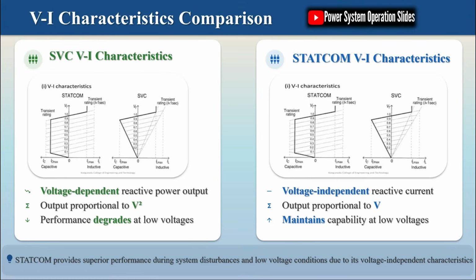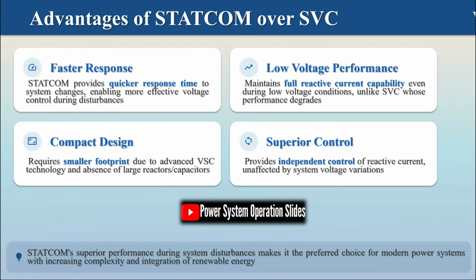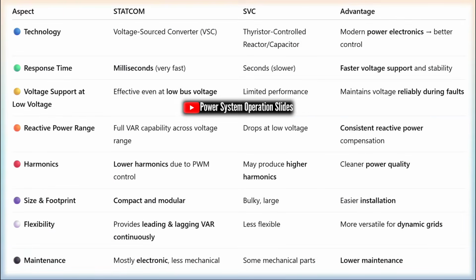The choice between SVC and STATCOM depends on various factors, including the specific application requirements, system conditions, and economic considerations. For applications where rapid response and full performance during low voltage conditions are critical, such as in weak grids or systems with high penetration of renewable energy, STATCOMs may be the preferred solution despite their higher cost. For more stable systems with less stringent performance requirements, SVCs may provide a cost-effective solution for reactive power compensation.